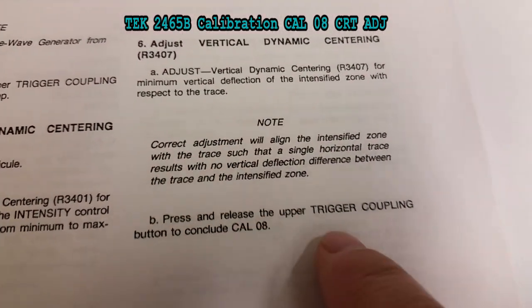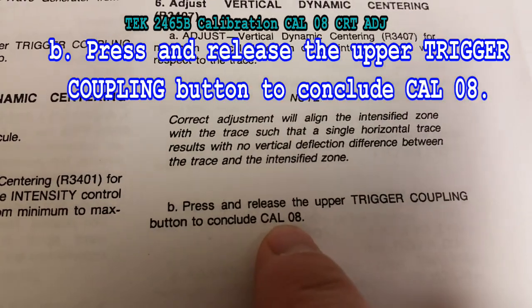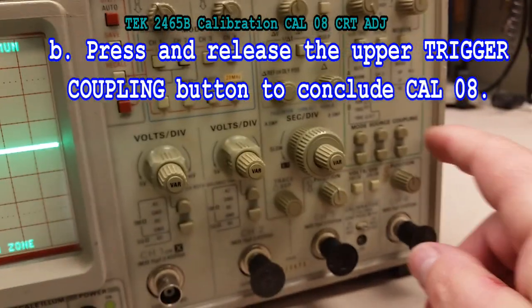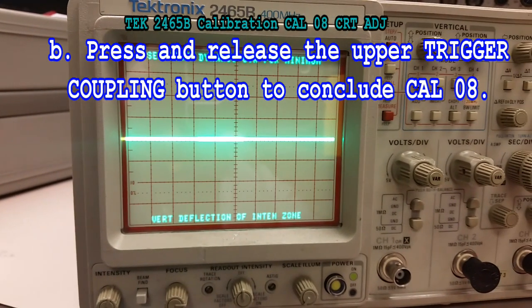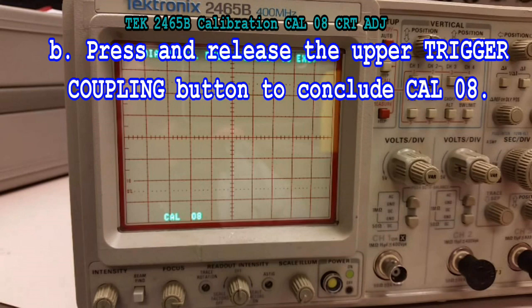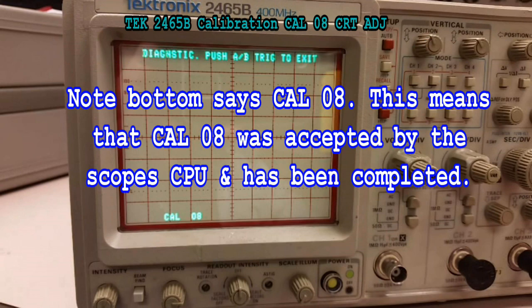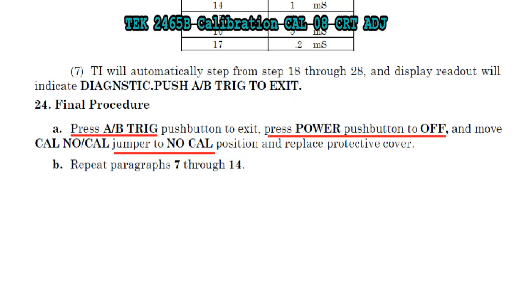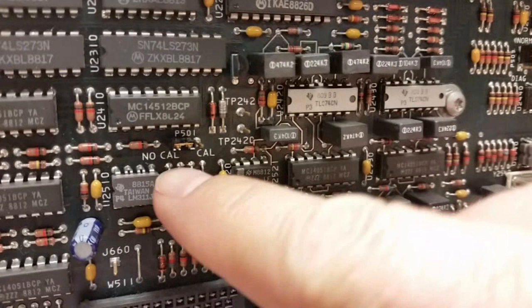And then when they get done with that, they want you to press and release the coupler. And that concludes Cal 8, which is your CRT adjustments right there, boom. And you can tell because after you hit the button, you end up with a Cal 8 on the bottom. So that means we've pretty much done it. That leaves one thing left, and that is, if you remember at the start, you have to actually tell the computer to put the Cal constants in. You do that by pressing the AB trigger, and then you turn the power off, and then you put the jumper over to the no Cal. Then you can turn it back on and check it, make sure everything's where it's supposed to be.